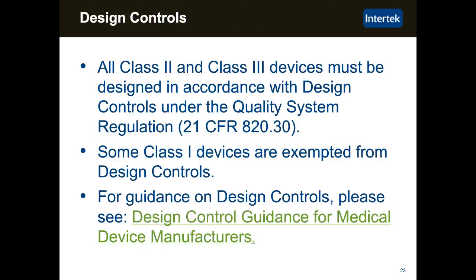All Class 2 and Class 3 devices must be designed in accordance with the design controls under the Quality System Regulation, Title 21 CFR Part 820. Some Class 1 devices are exempted from design controls. There is a guidance document from the FDA. If you enter design control guidance for medical device manufacturers on the FDA website, their search engine will take you to that guidance document.